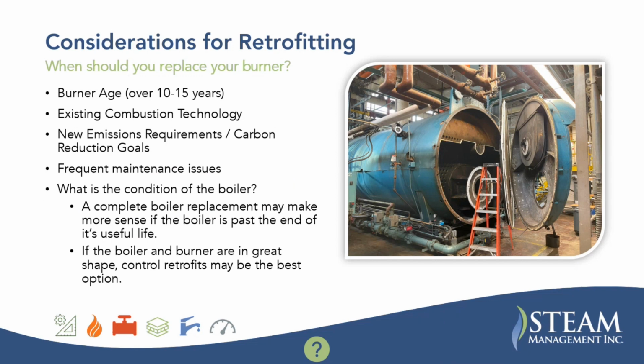Considerations for retrofitting. So when should you replace your burner? The obvious one is burner age. You start getting a burner that's 10 to 15 years old, it's maybe end of life anyway, so you're looking to replace it. And then you're concerned with, okay, what are the efficiency benefits here? We got another poll here, so please participate in that. Get some kind of feedback.